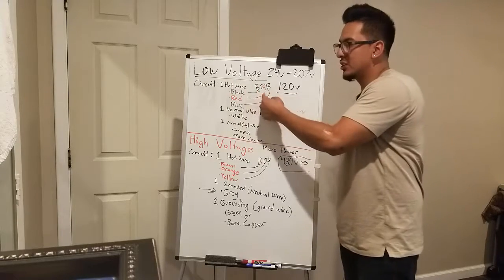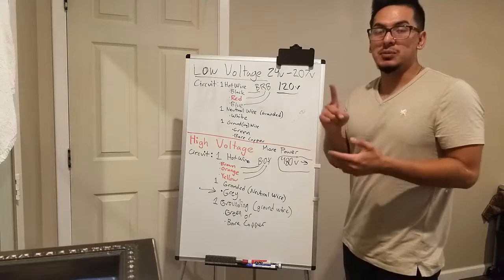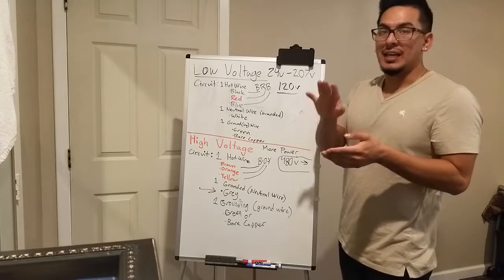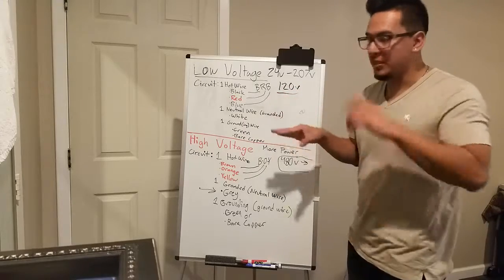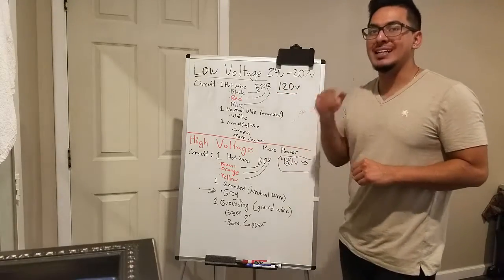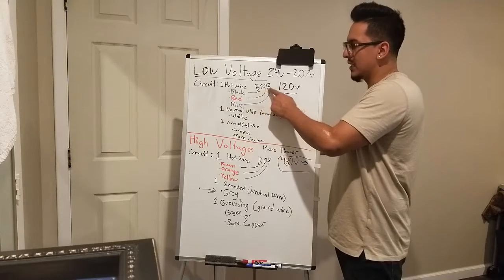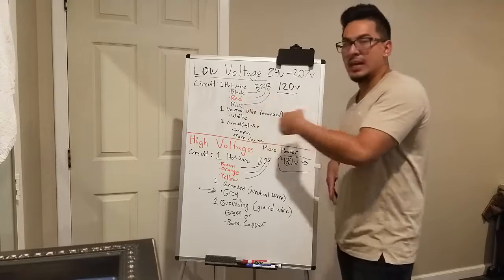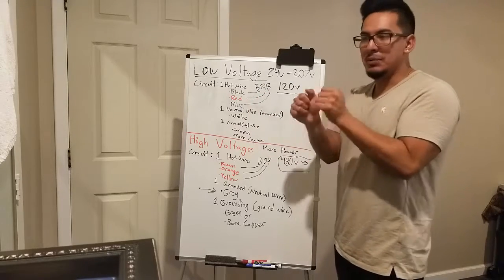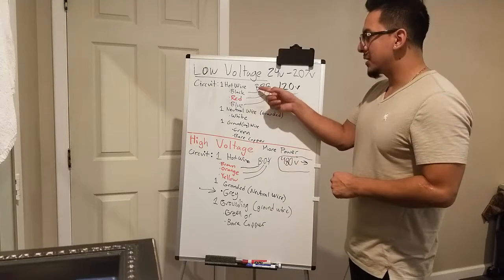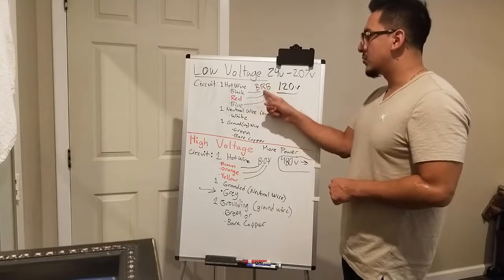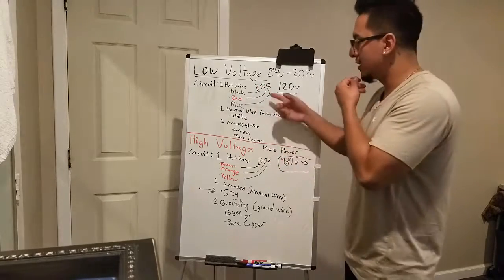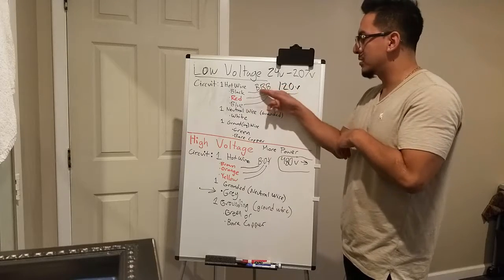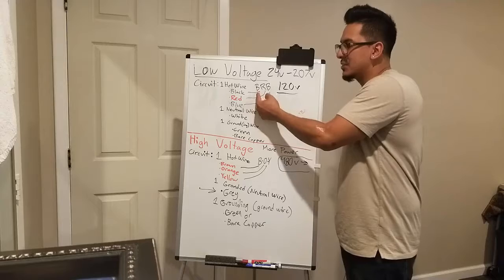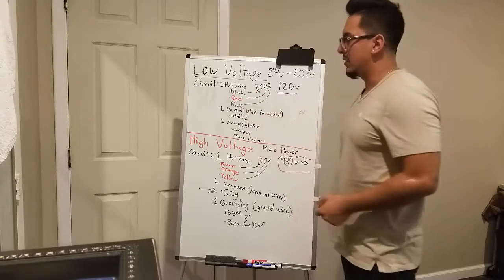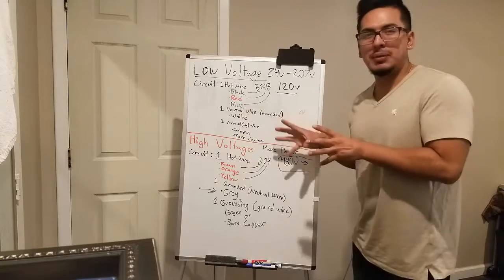So with low voltage, the hot wire is going to be one of 3 colors: black, red, or blue. I'll go into more detail on this shortly, but make sure you remember it in that order—that's why I wrote it this way. The way I remember it is BRB, like the texting acronym 'be right back.' It reminds you of black, red, blue for low voltage—not yellow, since there's no yellow in BRB—and it also gives you the order: black, red, blue.